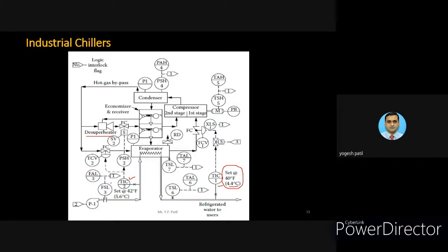So based on the inlet flow rate and based on this suction vane limit switch, the action can be taken by this controller. So then there is no closed loop found here. On the top side, you can see that the pressure is indicated over here, and there's a pressure switch also connected, and based on the pressure switch it is connected to the interlock.